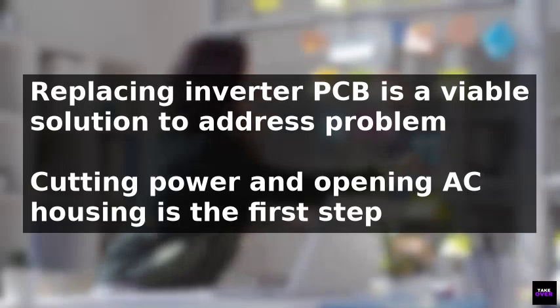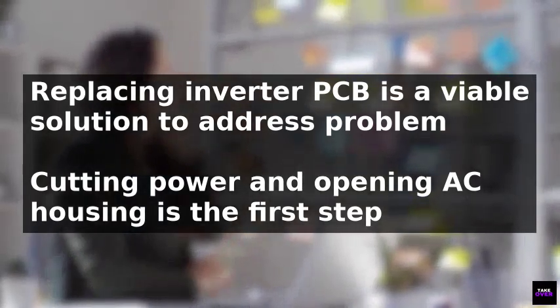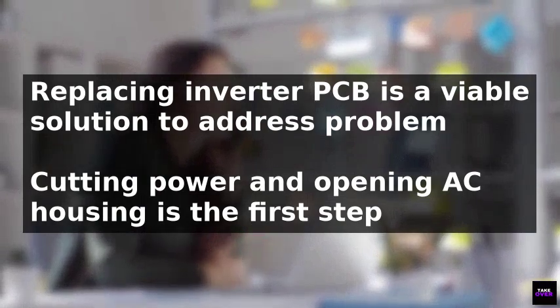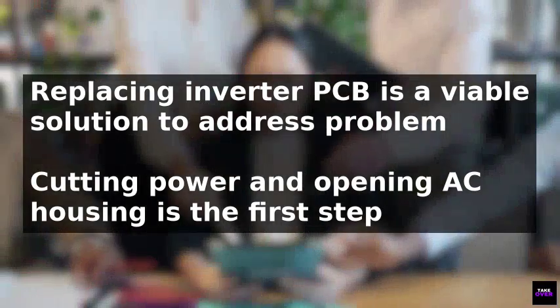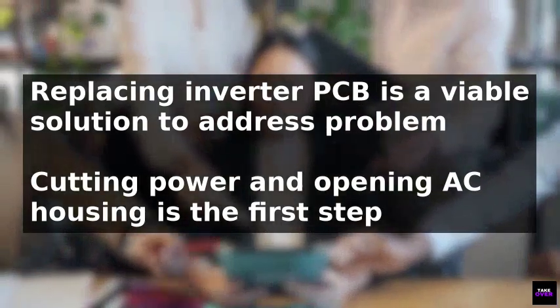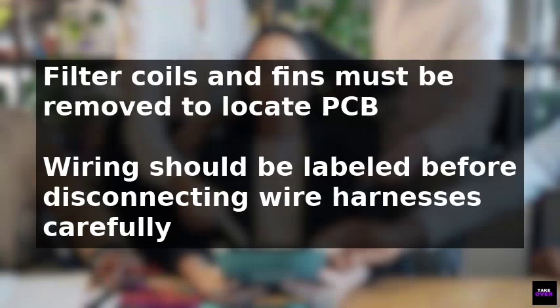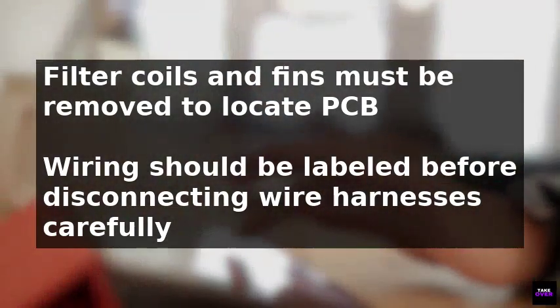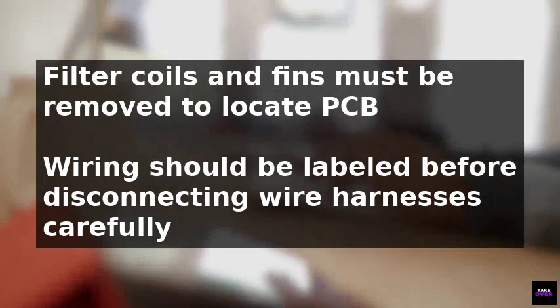This process involves cutting the power to the air conditioner, opening the AC housing, and taking a picture of the components for reference. The filter, coils, and fins must be removed to locate the PCB, and the wiring should be labeled before disconnecting the wire harnesses.